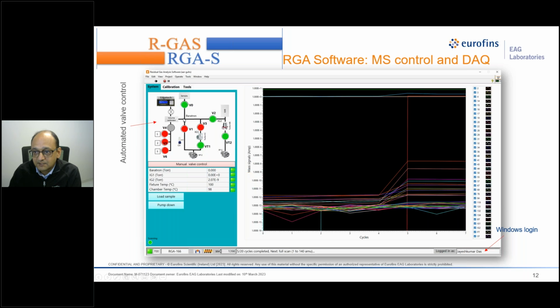So the sample chamber is in this region, and we are looking at the background of the mass spec, the background of the sample chamber, including the mass spec volume. Once that is done, there will be an interactive window asking us to introduce the standard gas to the system. Once we do that, it will start the scanning, and we go for another 20 scans, so 5 to 24. At that time you can see the increase in the signal. That's because we introduced the gas.